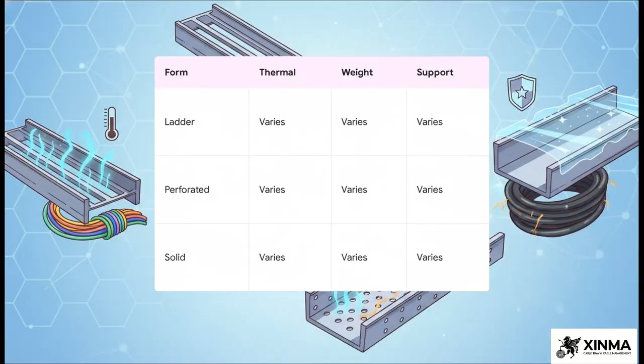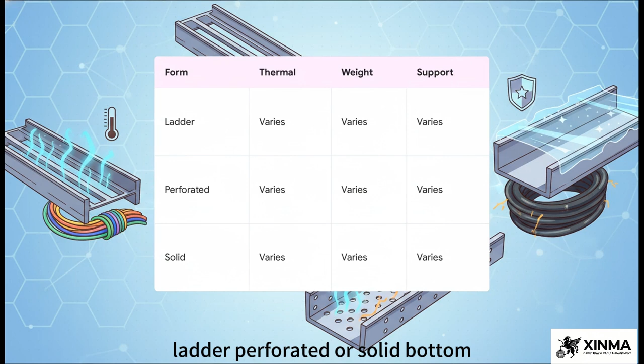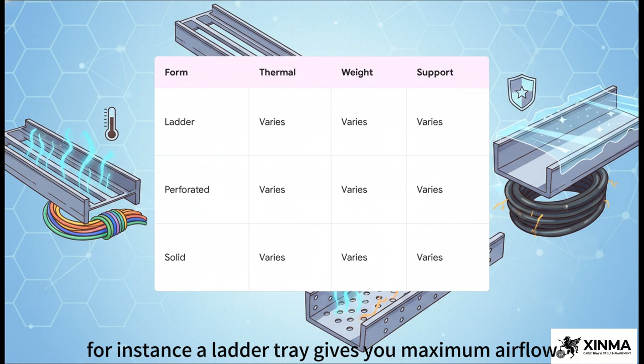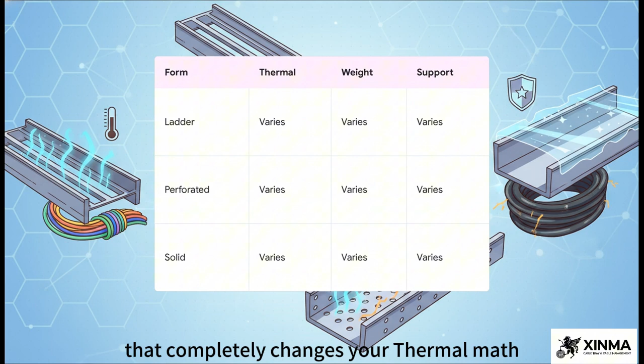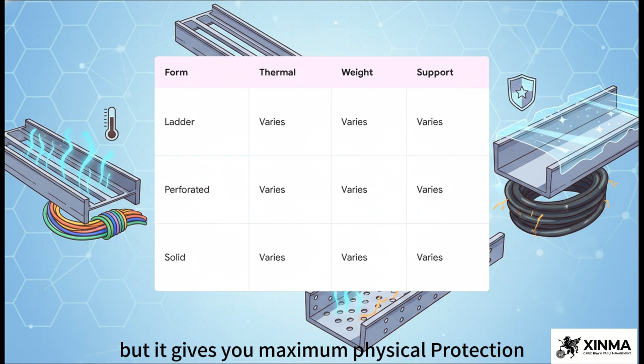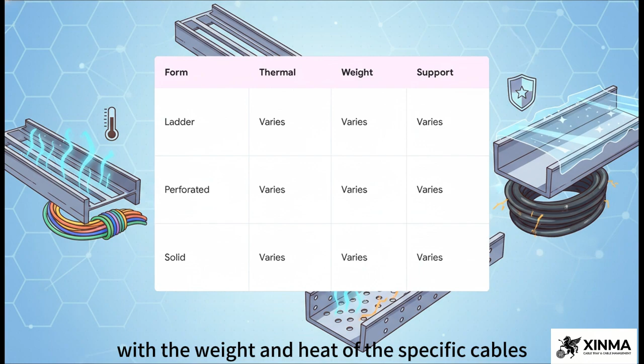Section 3, choosing the tray form, because the finish is really only half the battle. Procurement teams have to evaluate the actual physical architecture, ladder, perforated, or solid bottom, and notice how their performance profiles vary wildly. For instance, a ladder tray gives you maximum airflow for high heat cables, completely changing your thermal math compared to a closed system. On the flip side, a solid bottom tray sacrifices that airflow, but gives you maximum physical protection from falling debris. You've got to align the form perfectly with the weight and heat of the specific cables you're running.